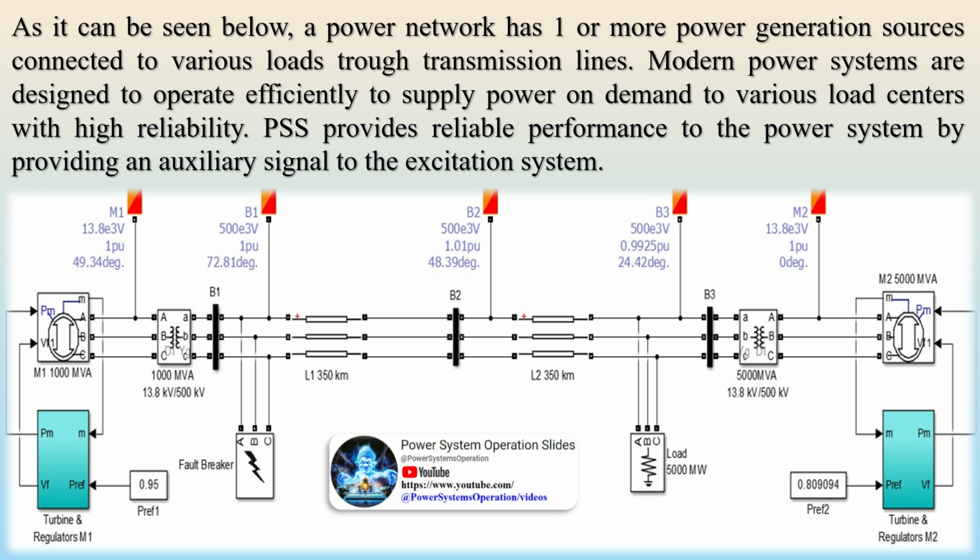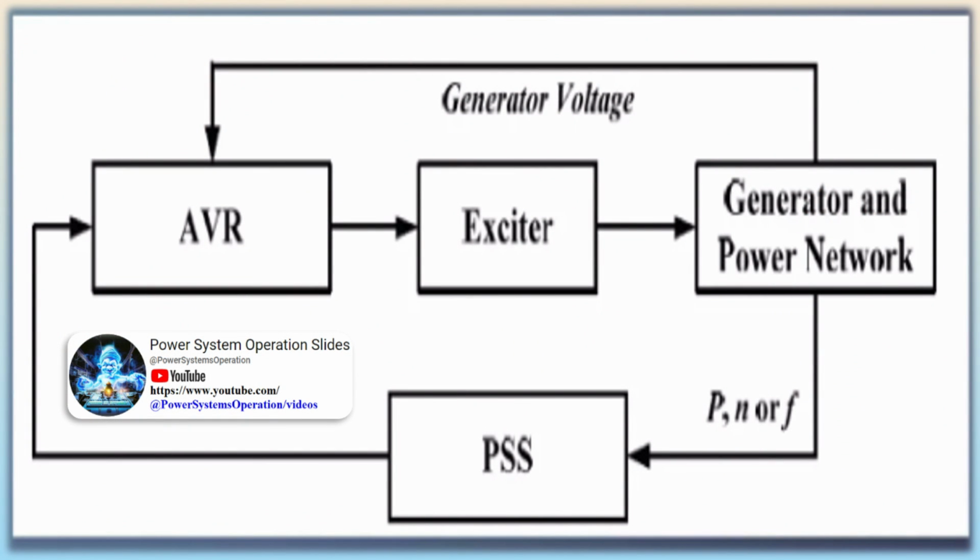Testing of the AVR PSS controls. Testing of the PSS is normally performed during plant commissioning. The test condition for PSS is at or near base load output of the plant. The testing of modern excitation systems is facilitated by the use of internal data recording and test signals. The basic types of tests usually performed are given in the following list.